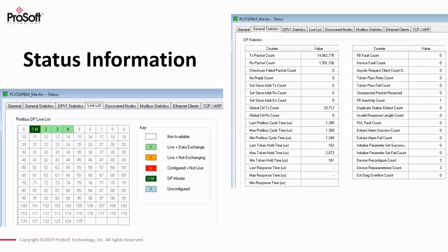So in addition to the status information of the module, you've got general statistics on the Profibus DP network that shows you everything from packets received to packets transmitted, and whether or not there were errors. It gives you some information regarding what your cycle times are and your hold time. And then also there's a live list. You could use the live list to put a module out on the network and determine what devices are out there, what devices are in data exchange, or what devices are live and not in data exchange. So there's quite a bit of information available through the live list.